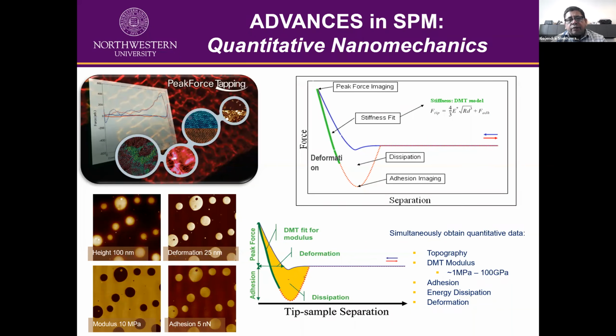In this category, the first one is the peak force quantitative AFM, which was developed by Bruker a few years back. That basically brought in a lot of advances in the scanning probe microscope. In the conventional AFM, you have a contact mode and a tapping mode, where contact mode is mostly used for high resolution and tapping mode is usually used for measuring soft materials. But with peak force tapping, we know that there are two primary causes of tip and sample damage. Any lateral force that the tip exerts on the sample can cause the sample to tear, as the tip plows through the sample.